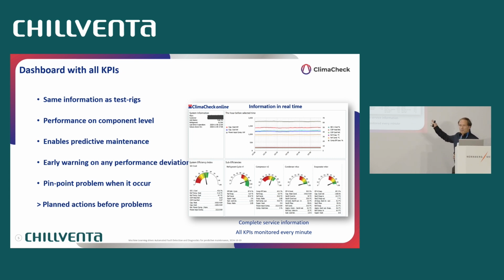Then we have a perfect service protocol. And you can monitor it 24/7 and indicate any deviation long before you have a failure. Most compressor failures in the industry are not because there is a problem in the compressor. It's because you're running it in a poor way. So there is almost always an explanation in the history of how you operate before it fails. And you can detect the faults on component level this way.